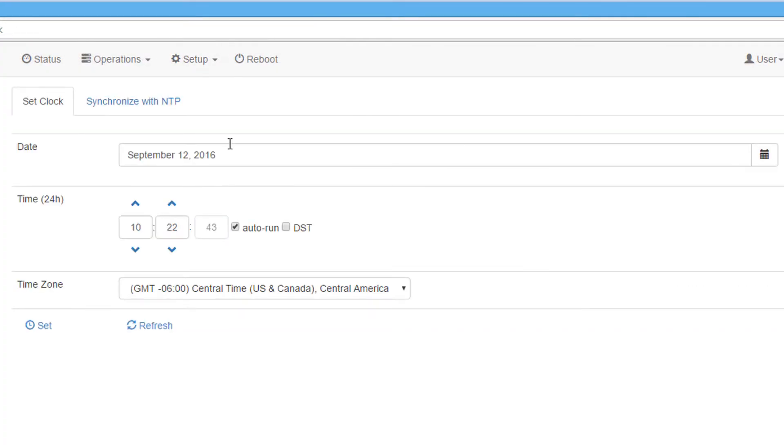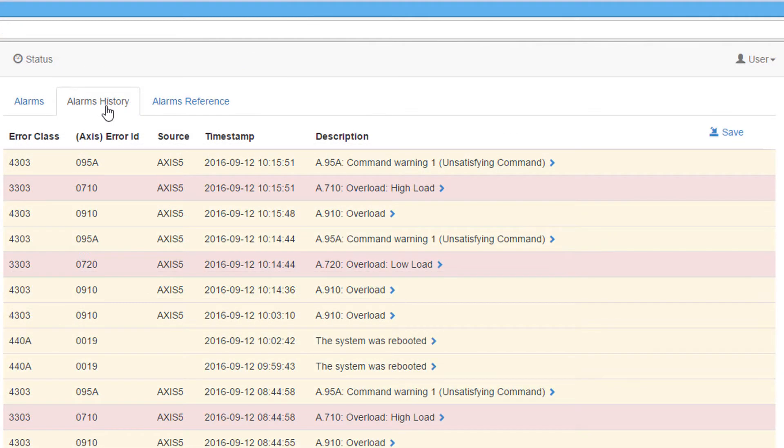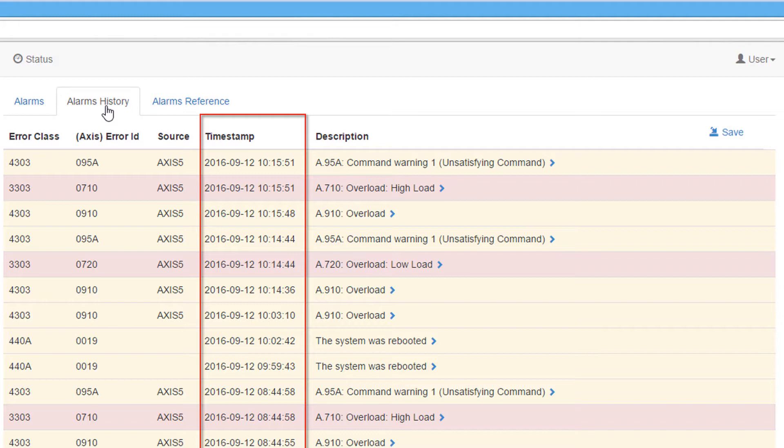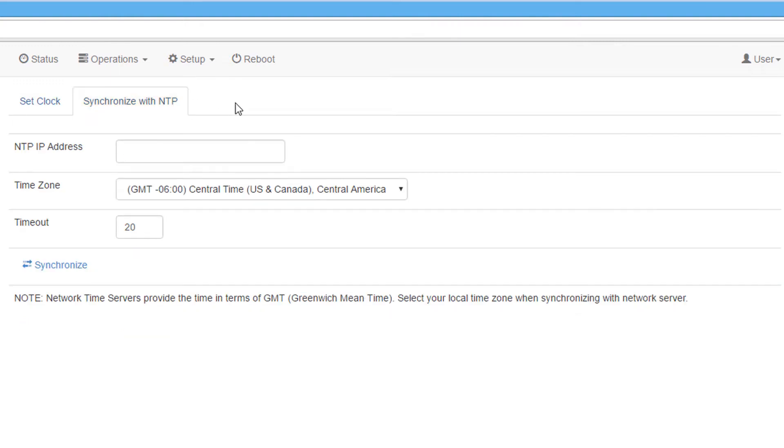The set clock function allows the motion controller's internal clock to be set. Setting this clock allows correct timestamps to be placed on alarms that occur on the controller or servo amplifiers. The clock can be set manually or it can be synchronized with the network time server or NTP server. This will only work if the controller has access to the NTP server.